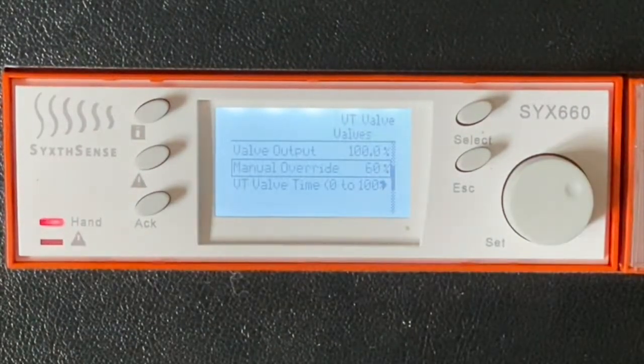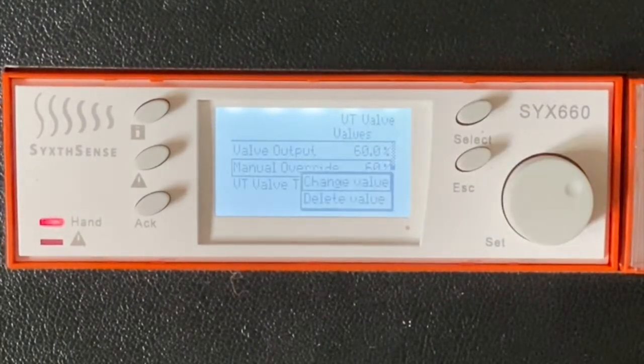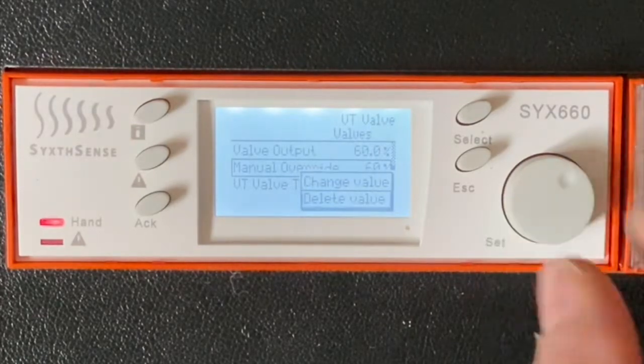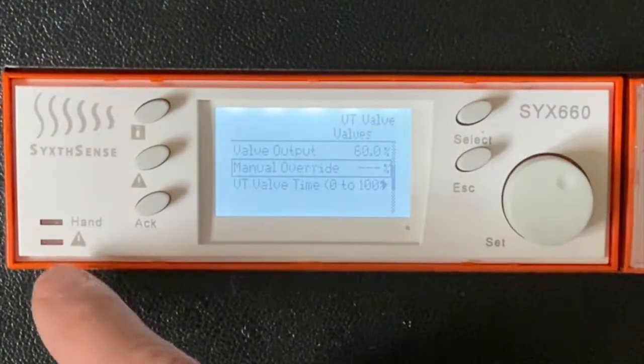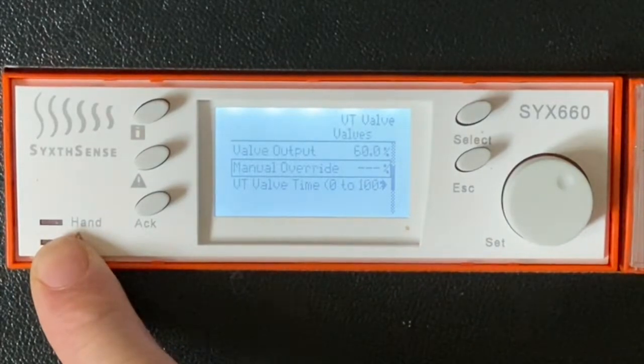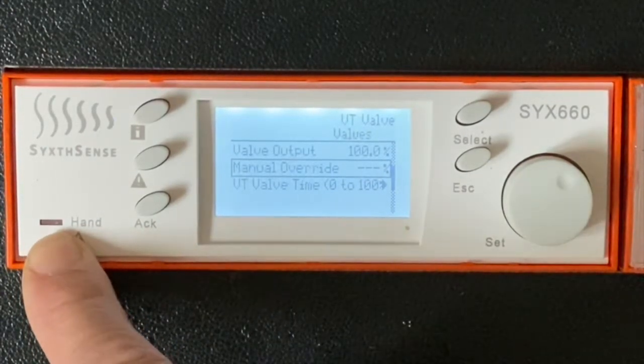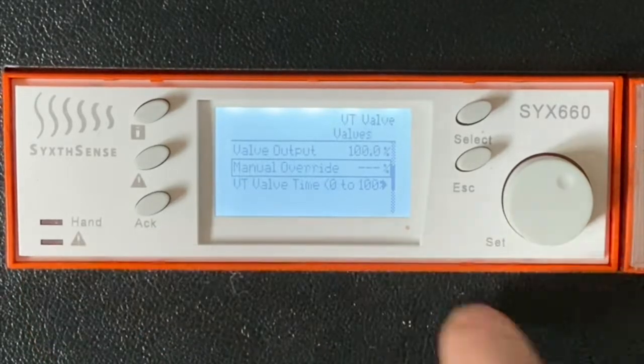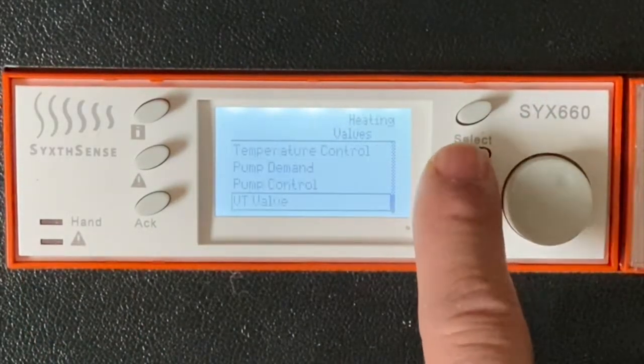The hand light has come on, and the outputs have started to drive the valve. We can then visually check the valve is driving the correct direction, make sure the valve is correctly allocated into the pipework, and then once we're satisfied that everything's okay, we can press the select button on the valve on the manual override parameter, and then we delete the value. We wait for the hand light to be extinguished before we'll get auto control. Okay, so that's complete. Press escape.